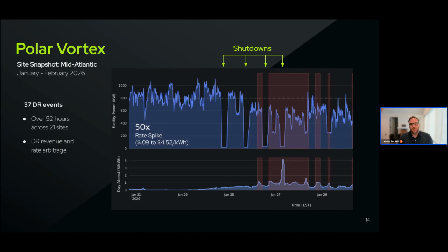You also have demand management here, which is different than demand response. In a market like PJM, you have coincident peak events, which are whenever the grid is most stressed, meaning the highest demand and lowest supply, or there's some sort of transmission delivery issue, something broken, whatever it is.